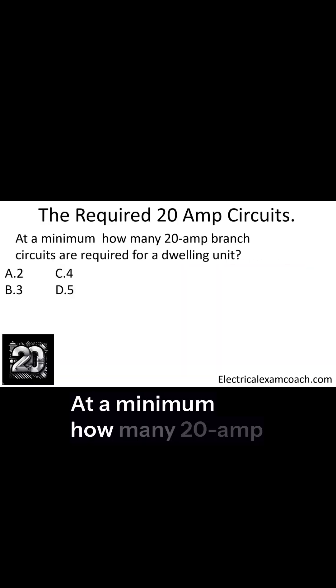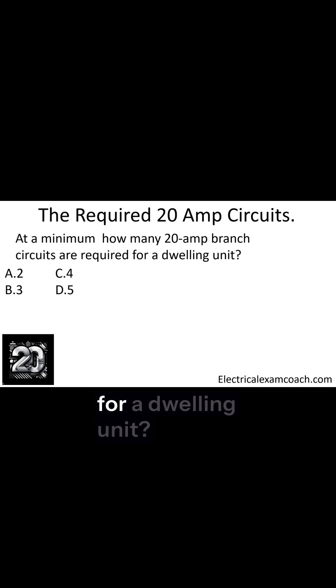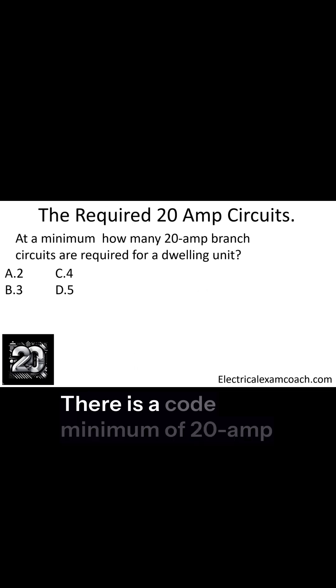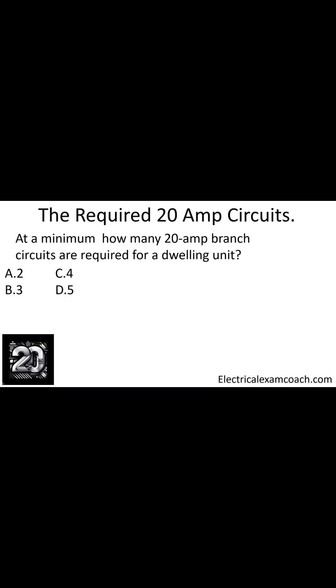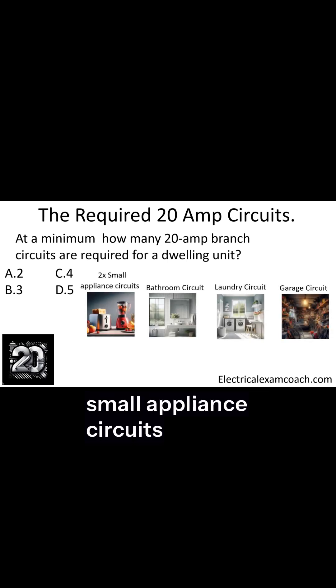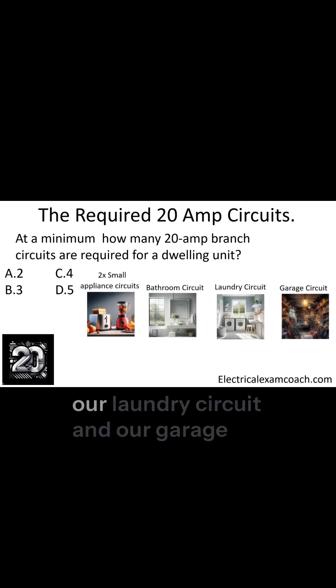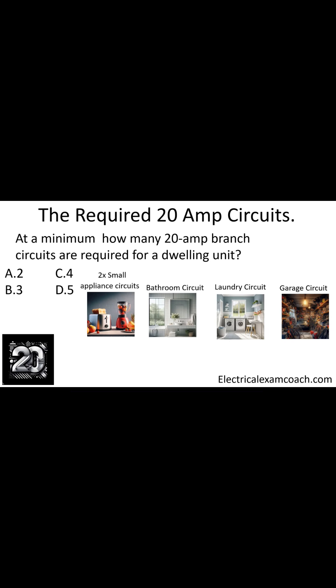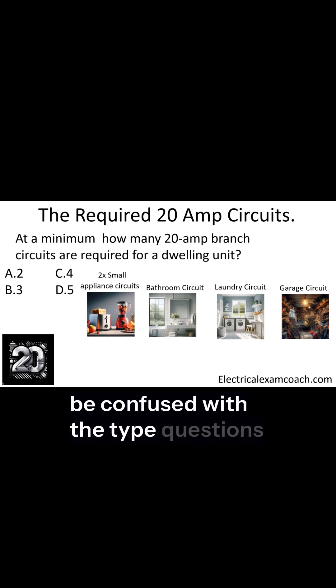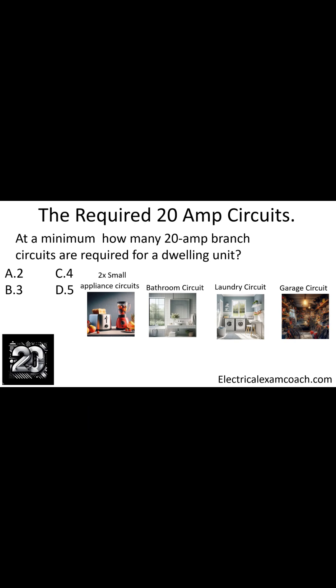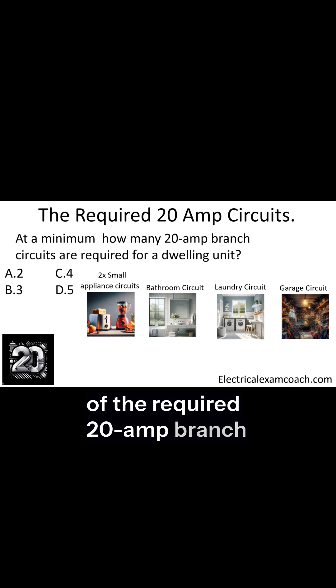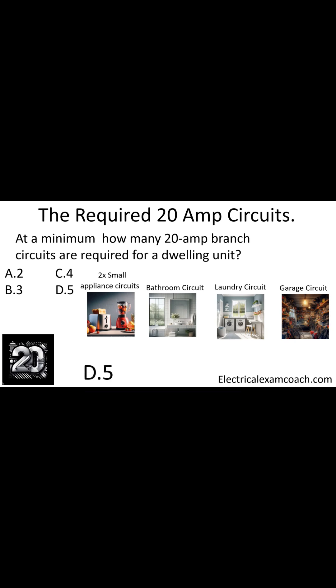At a minimum, how many 20 amp branch circuits are required for a dwelling unit? This is asking a very specific question. There is a code minimum of 20 amp branch circuits required in every dwelling unit. The correct answer is five. It's going to include our two small appliance circuits, our bathroom circuit, our laundry circuit, and our garage circuit. These are the code minimum of the required 20 amp branch circuits in a dwelling, and the answer is five.